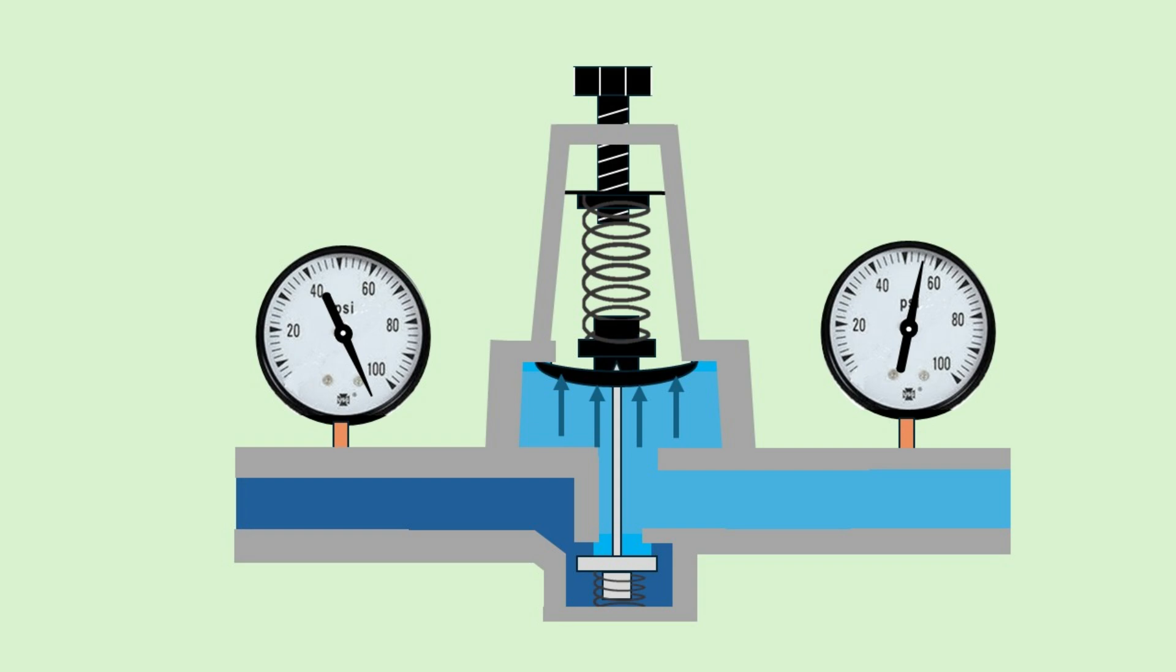As the diaphragm moves upward, it allows the poppet valve to close slightly. This restricts the flow of water, preventing the outlet pressure from rising significantly. As a result, the regulator restores the outlet pressure to its original setting of 50 PSI almost instantaneously.